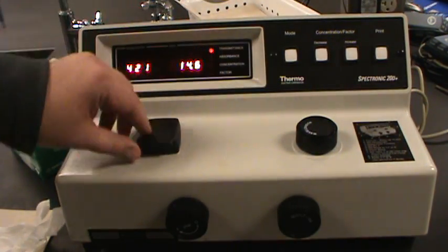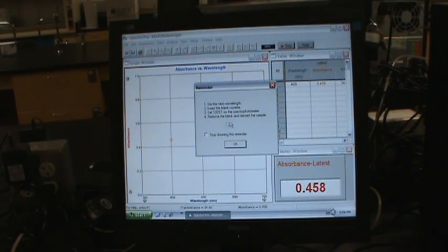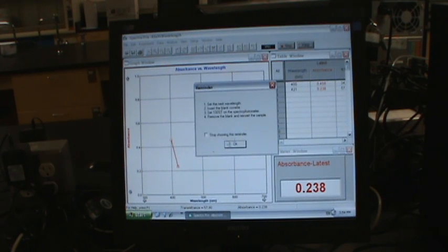Sample back in the instrument and back to the computer. So I set the new wavelength, I inserted the blank, I set 100%, I put the sample back in, okay. There's my next point. The absorbance has gone down. Keep, it's building my graph as I go, and it keeps prompting me to do the next step.